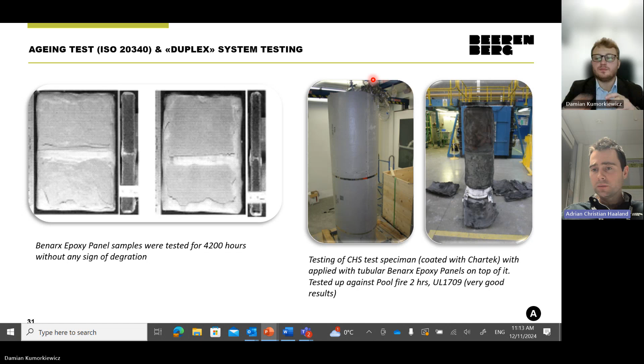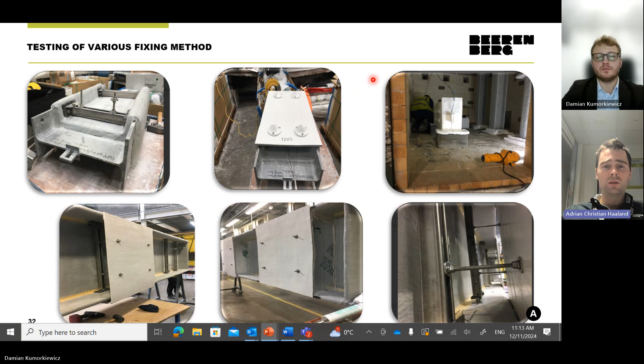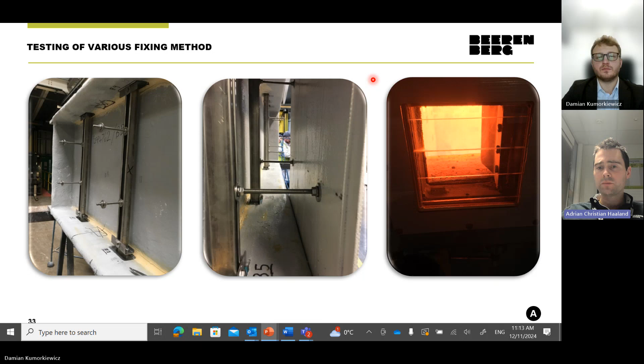Here you see some detailed furnace testing of special fastening methods, bolted studs and tensioning profiles used for a 2- and 3-sided application. And we did this to verify that the fastening method would not be adversely affected by the wet applied PFP on the beam, and also by the heat ingress through the bolted connections. A tensioning profile is basically a steel rod which you can tighten to push out against the two flanges and get a secured connection anchor point to bolt on with the panels.